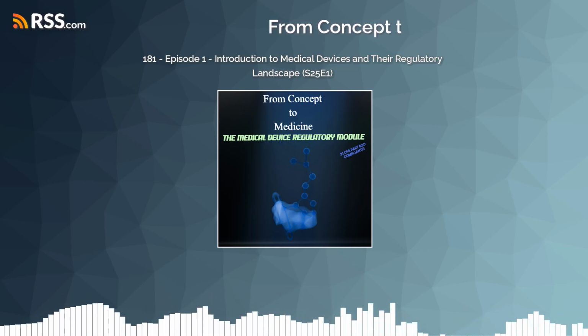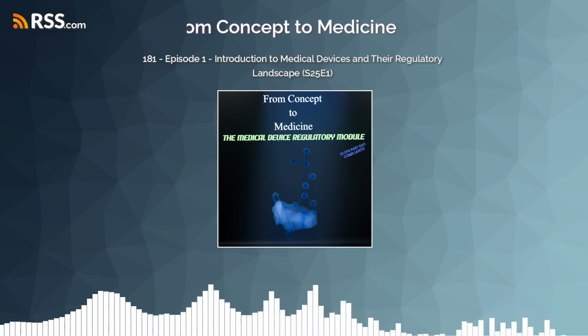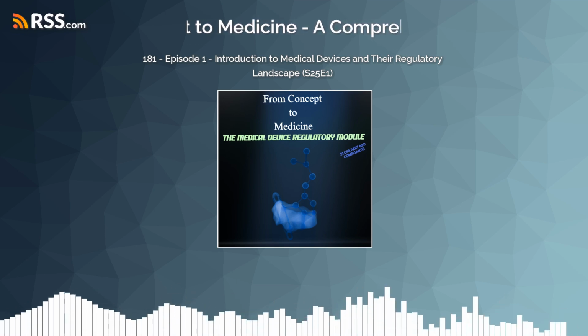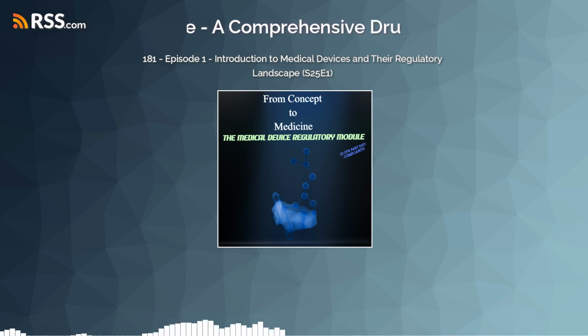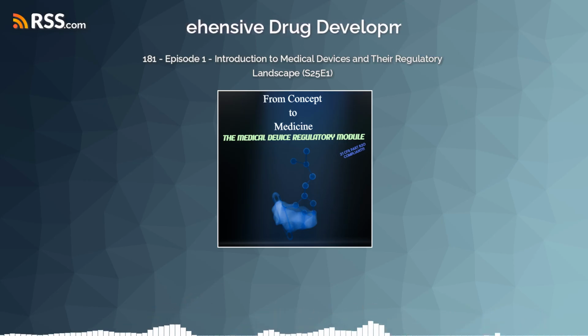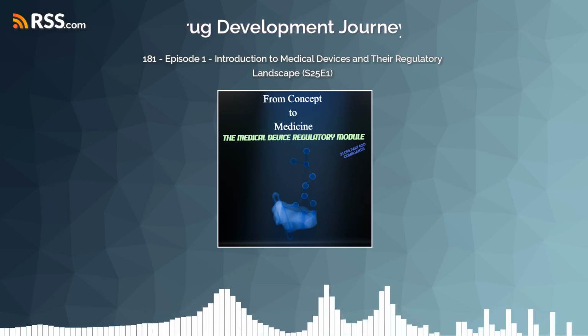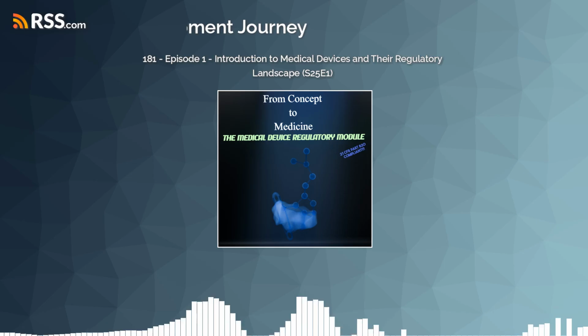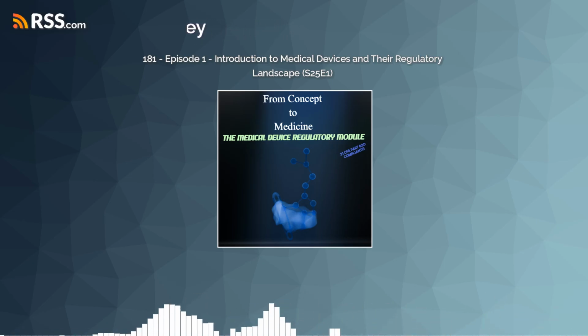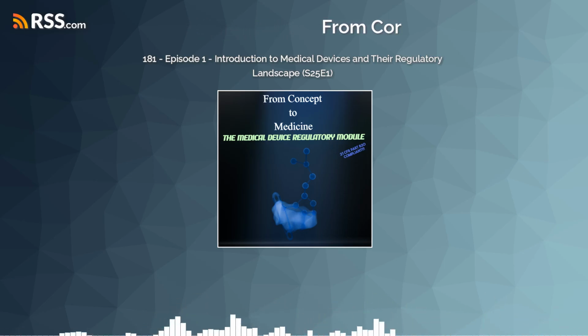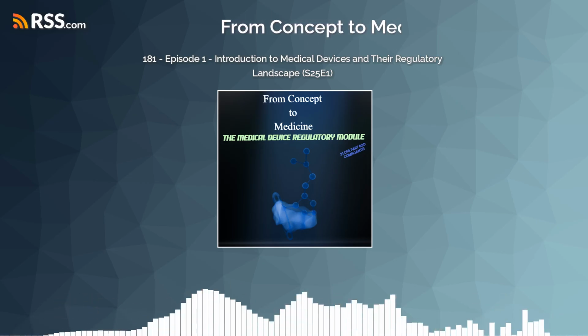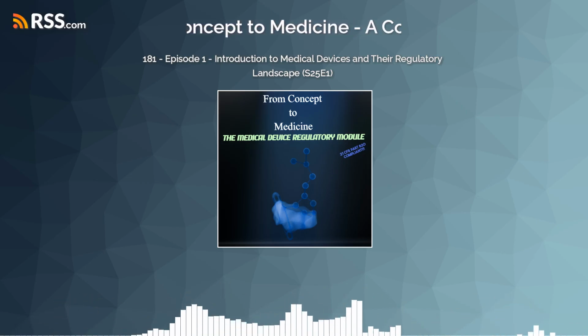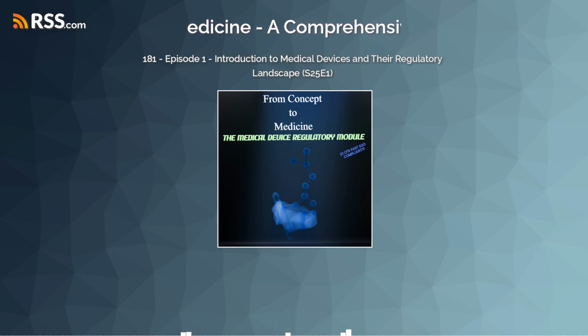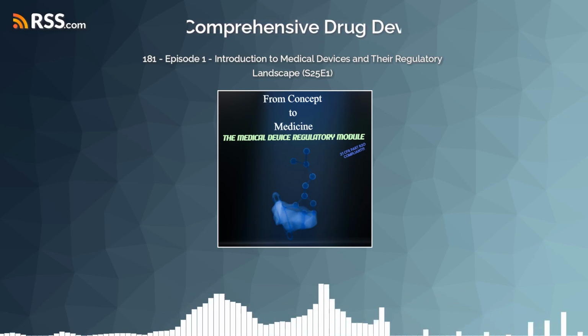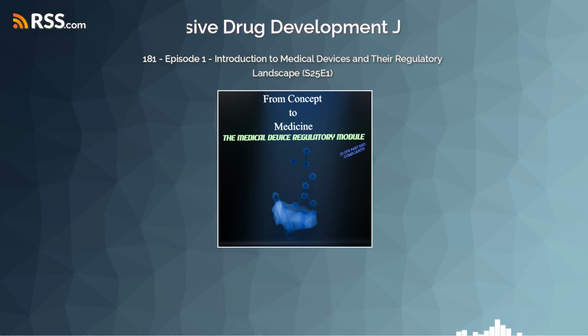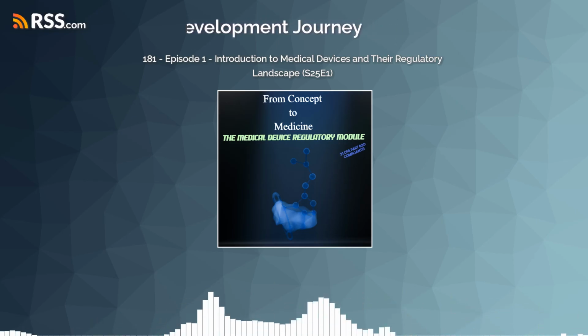It really sounds like the absolute mantra here is, if it isn't written down, it didn't happen, for the entire process. It truly is the bedrock of the whole system. Documentation and record keeping are paramount under the QSR. Detailed records provide that complete, traceable history of how a product was designed, made, tested, released, everything. Batch records, equipment logs, personnel training records, supplier evaluations, complaint files, audit reports. It's comprehensive. And in today's world, electronic records and signatures are common, governed by 21 CFR Part 11.